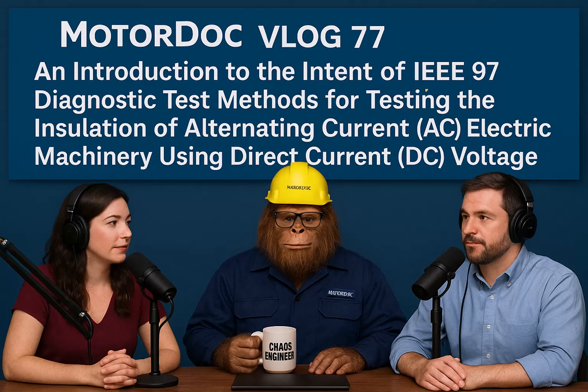Dramatically differently. Epoxy, polyester, older asphaltic systems, they each have unique dielectric properties, unique absorption characteristics, different levels of inherent conductivity. Knowing the material is fundamental. You need to know what a normal test result should even look like for that machine. Makes sense. And for healthy, new stuff, conduction should be low. Very, very low, ideally negligible.